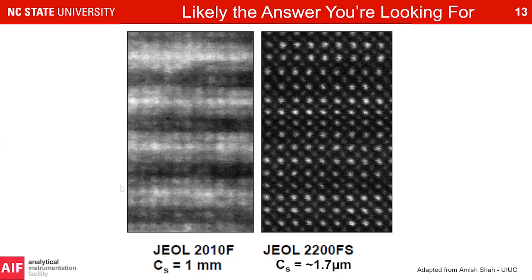Comparing an uncorrected TEM to a spherical aberration-corrected, probe-corrected system on the same material: in the uncorrected microscope, atomic columns are very blurry — the spherical aberration coefficient is on the order of millimeters. After correcting most spherical aberrations in the condenser lens, the atomic structure is clearly visible and the spherical aberration coefficient drops to microns. A dramatic drop in aberrations gives a huge rise in resolution.